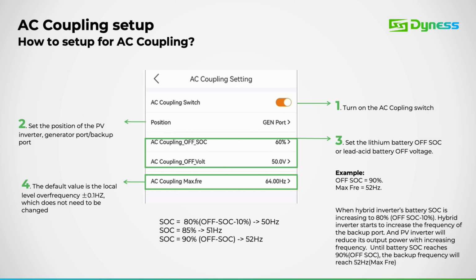This is the AC couple setting page. Here you can configure the position of the grid tie inverter and specify the conditions for stopping and turning it off. AC coupling operates using frequency.